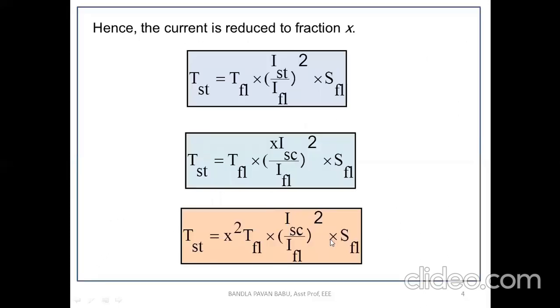So that is the reason. Initially, if we are not applying any type of resistance and directly we are starting, we can expect a huge amount of current. That is the short circuit current, so that is the maximum current. When we are applying this method, we are going to add the resistance and regulate the voltage. We don't know what the particular ratio is. If we consider it as X, obviously the current is also regulated. So it depends upon the factor X, or you can term it as K, that's up to you.